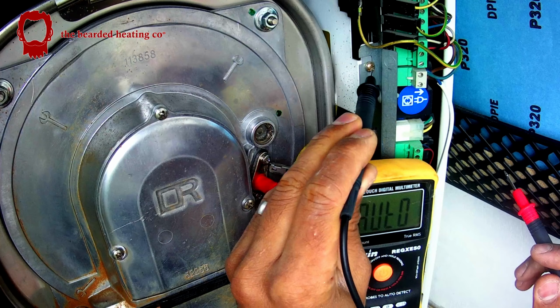Usually when it fires up the first time, the boiler will fire up and stay alight for a little while, proving that it's working, and then it'll just go to the dots. But right now it's still flashing in parameter mode doing self checks, and it looks like it's not happy. I think we're going to get an E4 - let's just watch it go to E4.